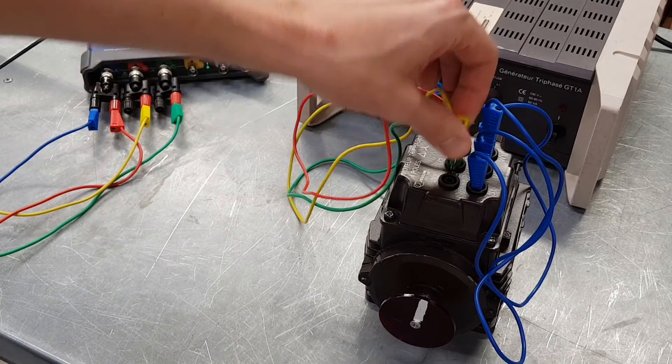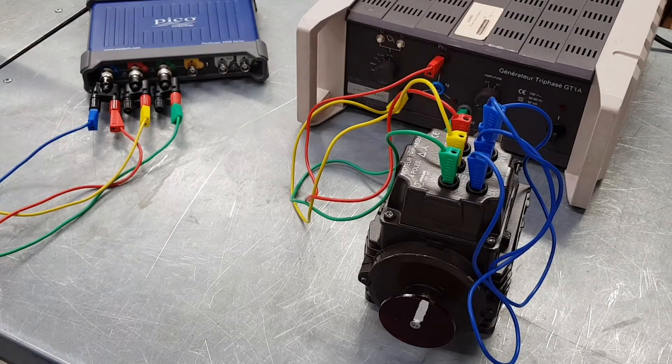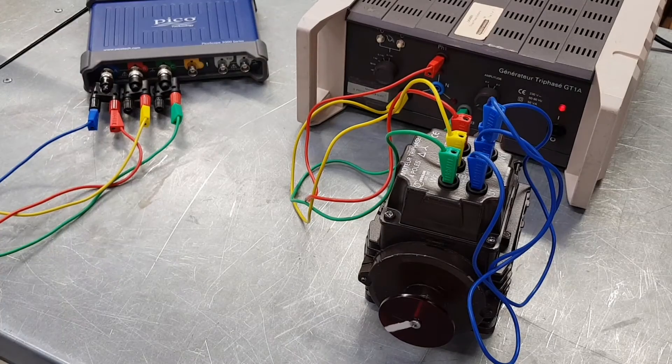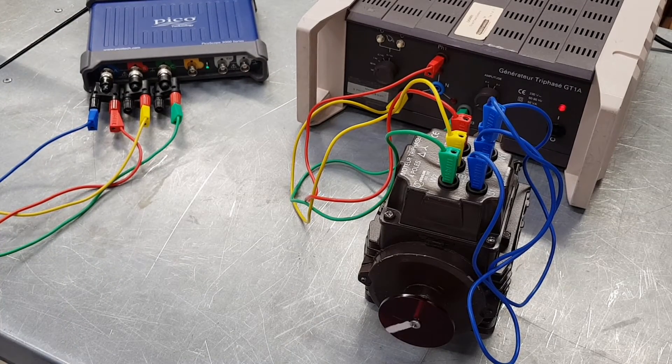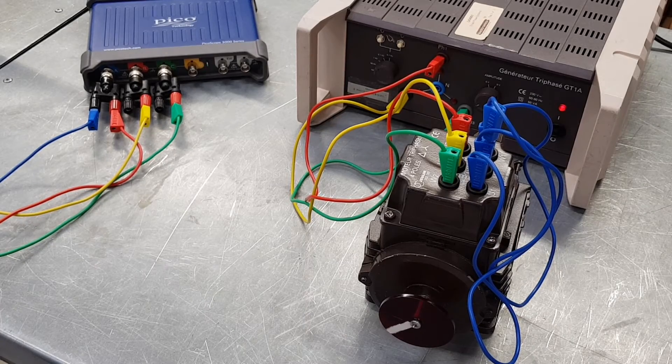Then if we swap over just any two of the incoming three-phase supply, and if we connect this up again, you can see there now we've changed the direction that motor goes in. So that is the easiest way to change the direction of the motor.